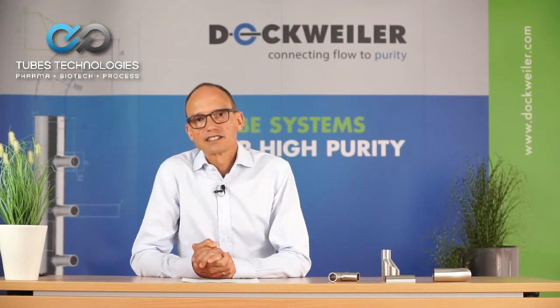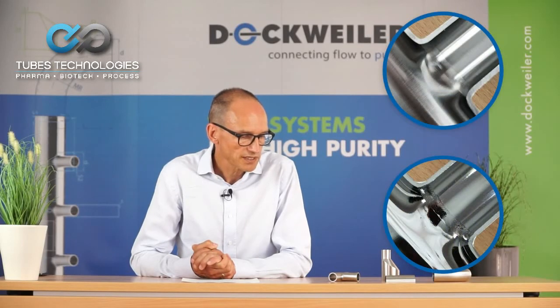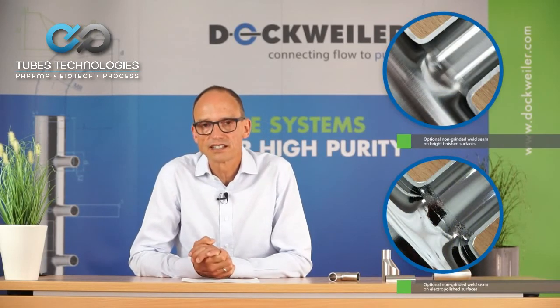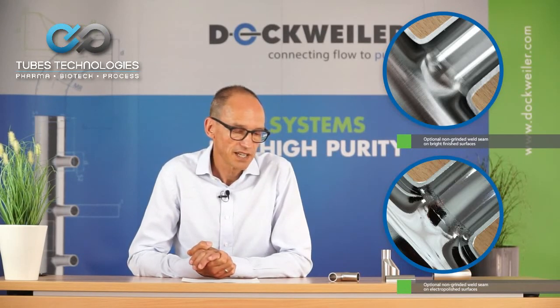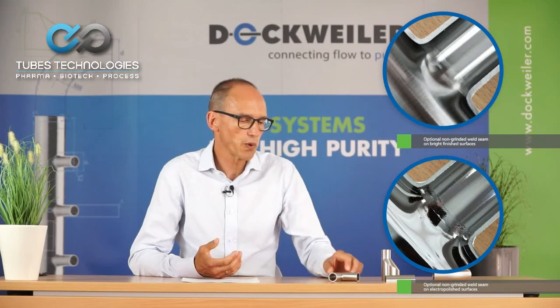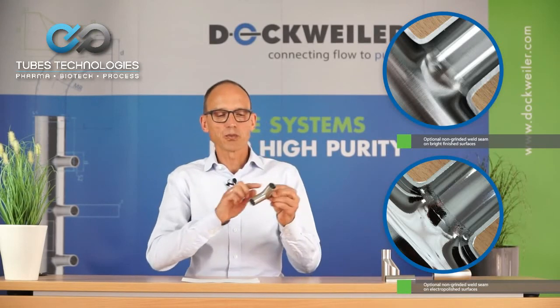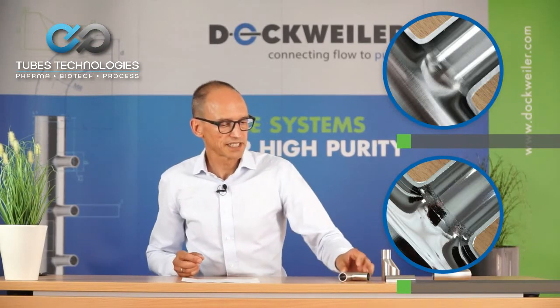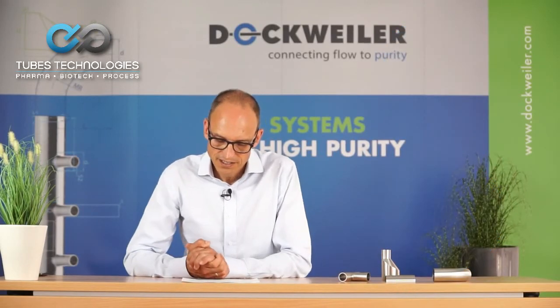So this is the first option, and the second option is to leave that T-piece weld in the as-welded condition, which has to meet the requirements of Table 18, which I mentioned earlier, and would be exactly the same requirement as the three other welds on the T-piece have to meet when getting installed. So that's the overview of the new revision of DIN 11865. The English translation is coming out soon.